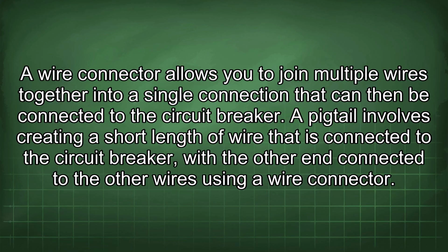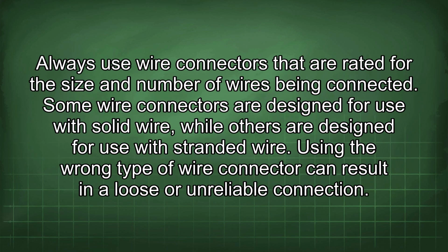A pigtail involves creating a short length of wire that is connected to the circuit breaker, with the other end connected to the other wires using a wire connector. Always use wire connectors that are rated for the size and number of wires being connected. Some wire connectors are designed for use with solid wire, while others are designed for use with stranded wire. Using the wrong type of wire connector can result in a loose or unreliable connection.